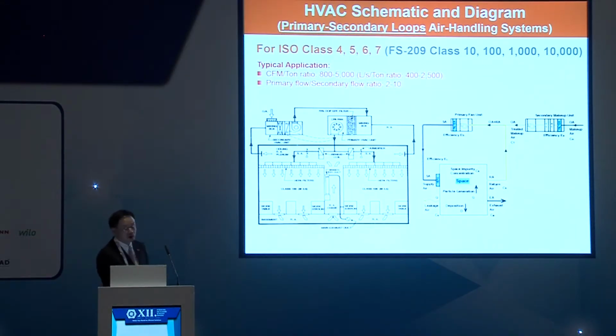Because the reason you use 2 units is that a single unit will not be able to handle the latent load properly. The airflow rate is so high, and maybe with a 2 degree or 3 degree delta T, you already meet the room temperature requirement, but there is no condensation inside the air handler unit. In other words, moisture control inside the clean room is not available.